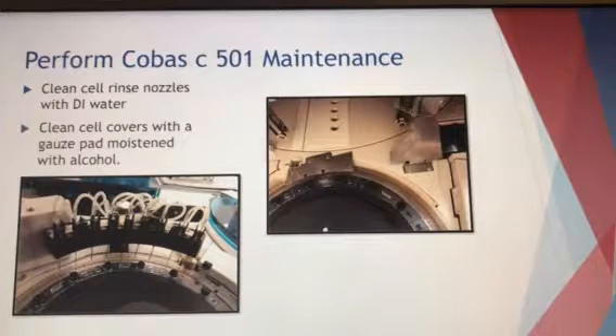By this time, your analyzer should be in standby mode, and double check just to be sure before you go opening anything. It will say standby mode up in the left-hand corner. Then you'll open the top cover for your 501 side, and you're going to first clean your cell rinse nozzles with DI water. Take a gauze pad, moisten it with DI water, and gently run it across each of those nozzles, which are in that first picture there. The second thing you want to do is clean your cell covers, which are in the second picture. There are those two silver covers. I left one up and one down just so you could see that there are two of them. Just take an alcohol pad and wash the front and back.